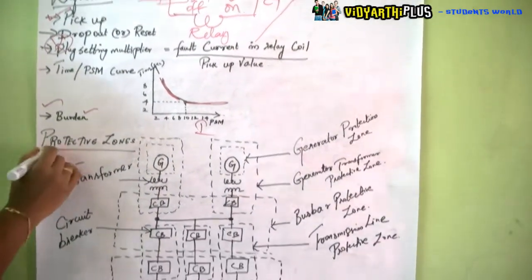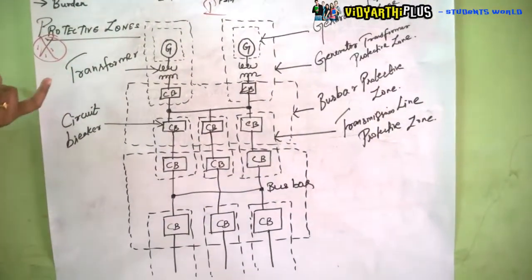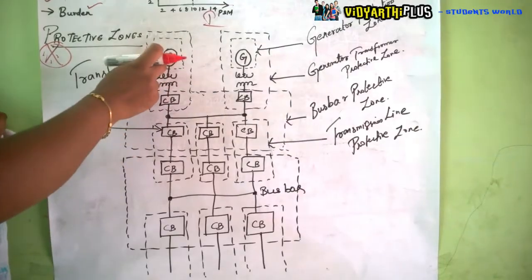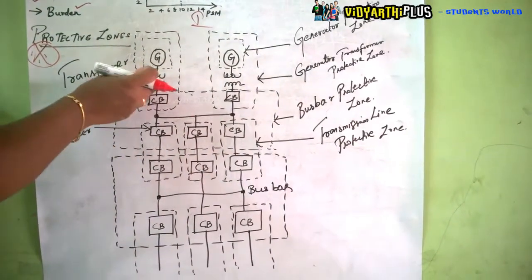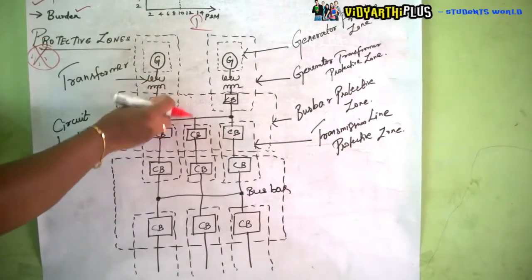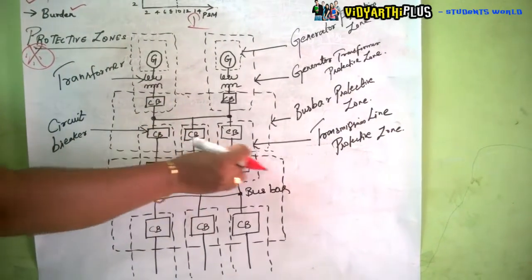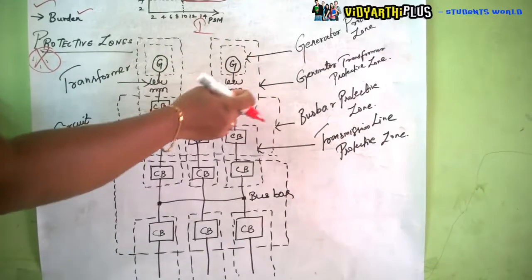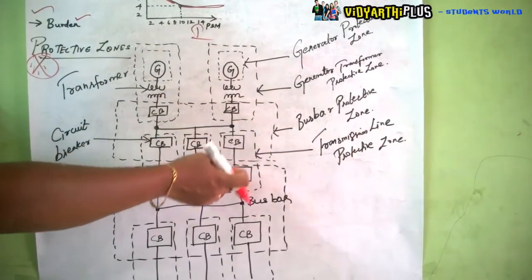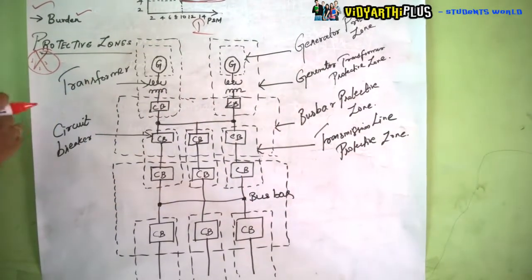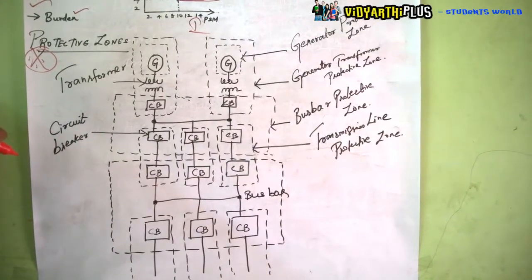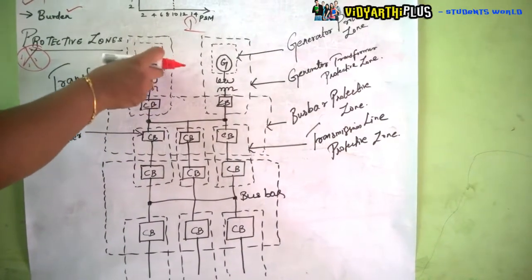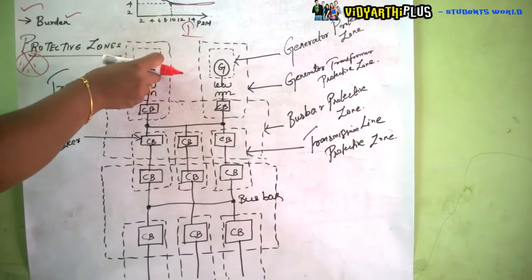Now we come to protective zones, a very important topic in relaying. The system includes a generator connected to a transformer and transmission lines, with a circuit breaker connected at every part for protection. There are four protection zones: the generator protection zone, the transformer protection zone, the bus bar protection zone, and the transmission line protection zone. If a fault occurs in the generator, a relay and circuit breaker in the generator protective zone will sense the fault and immediately isolate it from the rest of the system.